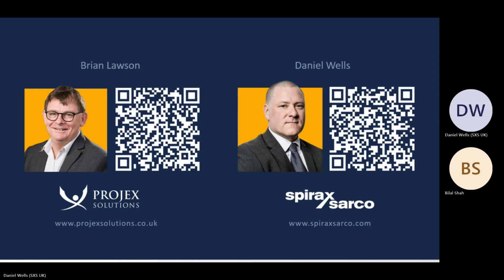Thank you. But there's problems with the steam condition that comes out of the boiler. So let's say we are having wet steam out of the boiler. Are there measures in place to maybe just heat that steam up a bit more? Yes, that's what we call superheated steam. For example, if you had some form of secondary heating element in the steam pipework as it leaves the boiler, like an electrical heater, you would create superheated steam.